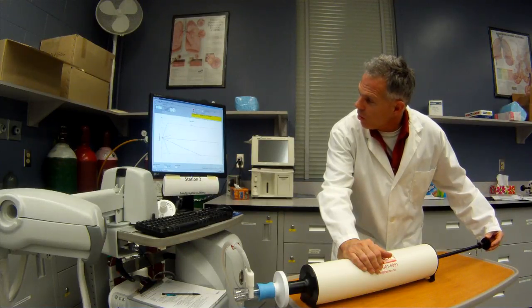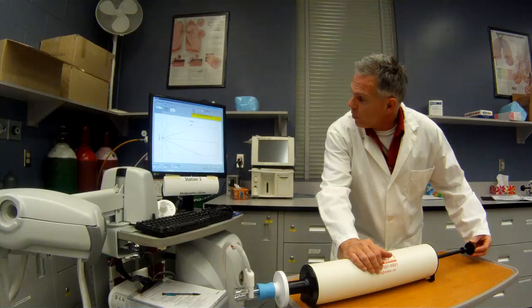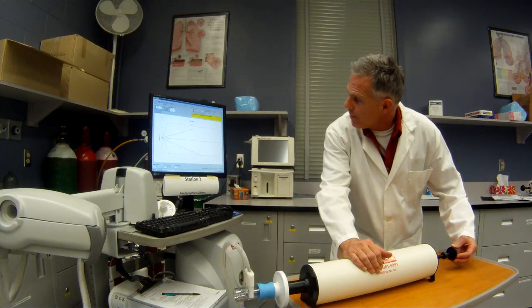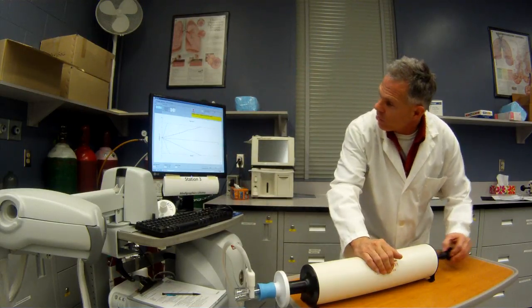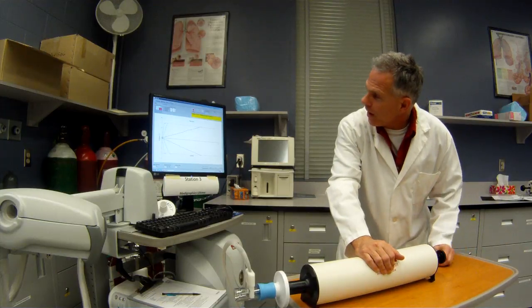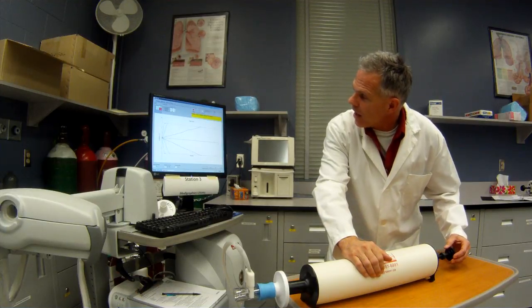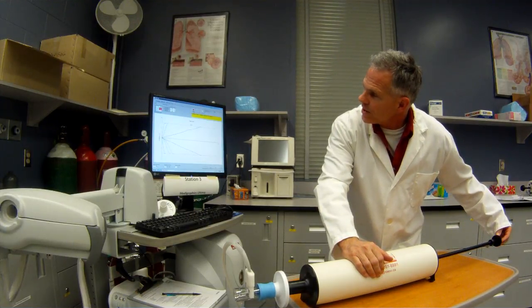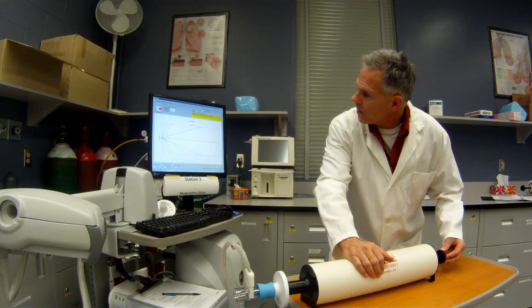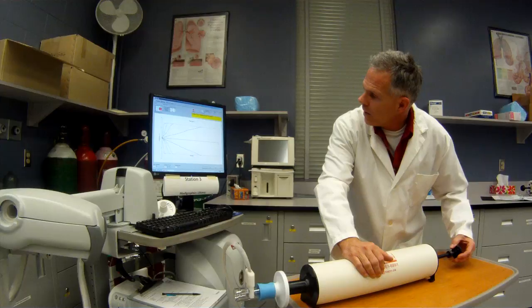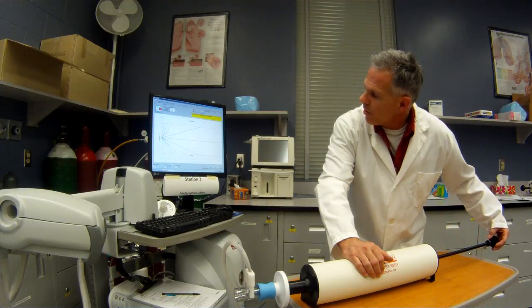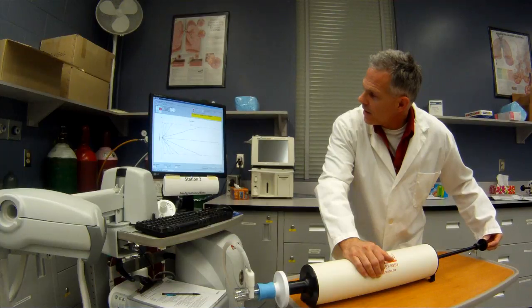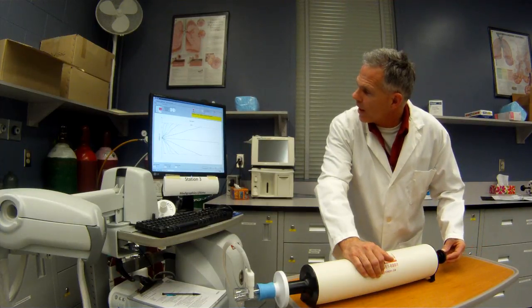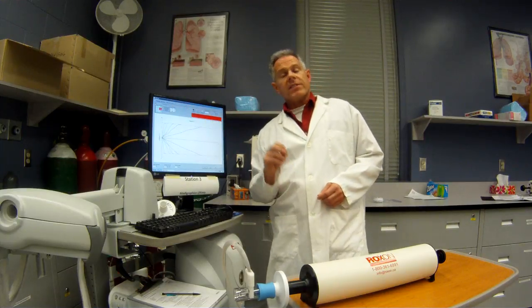Now, they don't have to follow the lines exactly as I'm doing here. With a little bit of practice, it's pretty easy to do that. But initially, you don't have to be following the lines absolutely exactly. Now I'm going to do a couple of high flows. All right. Okay. So we've got a little bit of an error here, probably because I might have hesitated a little bit, or it just might not be calibrated quite right. So I'm just going to do a couple other flow rates here. And we'll do a nice slow, medium kind of flow rate. So this one here has already given me a warning. On my higher flow rates, it didn't calibrate successfully.